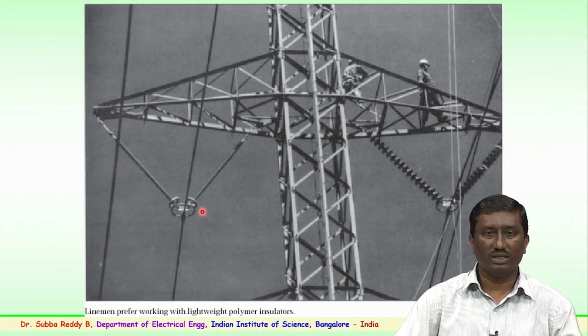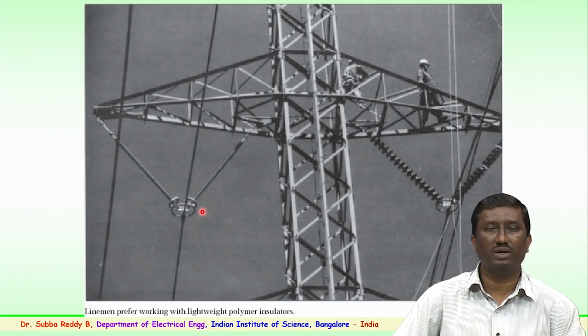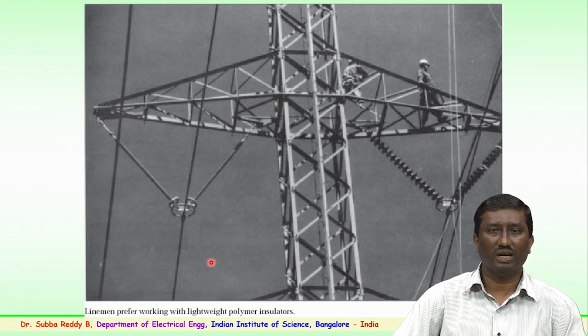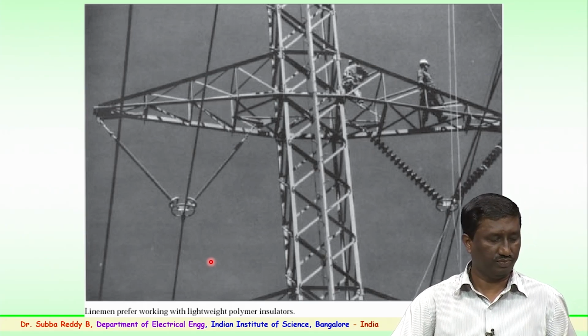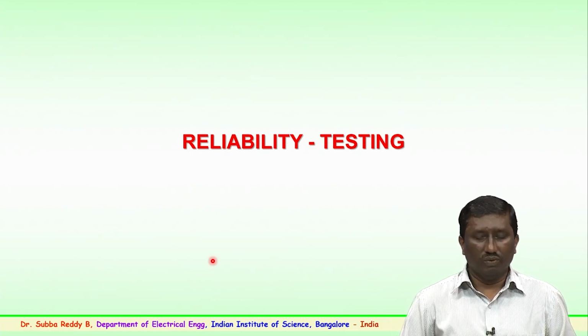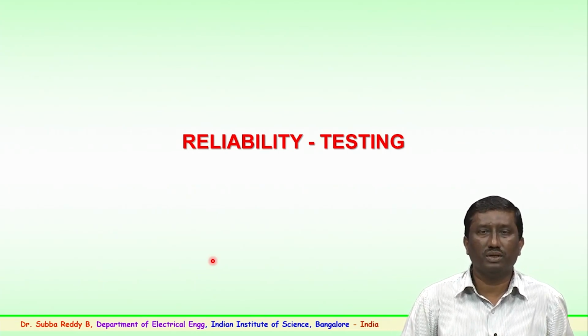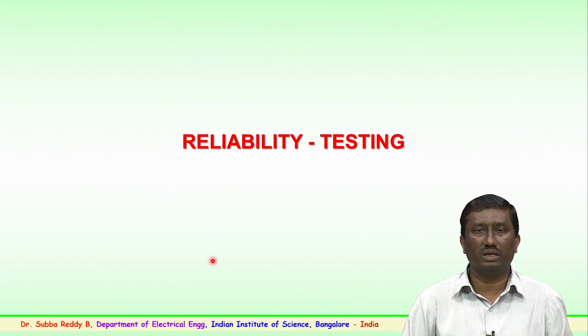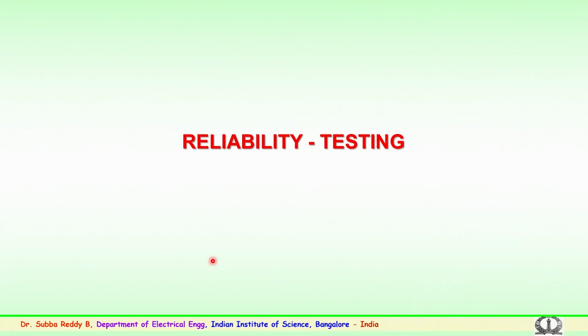That is where the technicians or the linemen prefer to work with lightweight polymer strings, which are more aesthetic and have less weight, and it is much more comfortable for the people to work in the high voltage and extra high voltage transmission systems. So, we were looking at various types of insulators which are being used for high voltage, EHV, and UHV transmission. We will look one by one into the reliability and the importance of the testing for the ceramic, glass and the polymer based insulators.